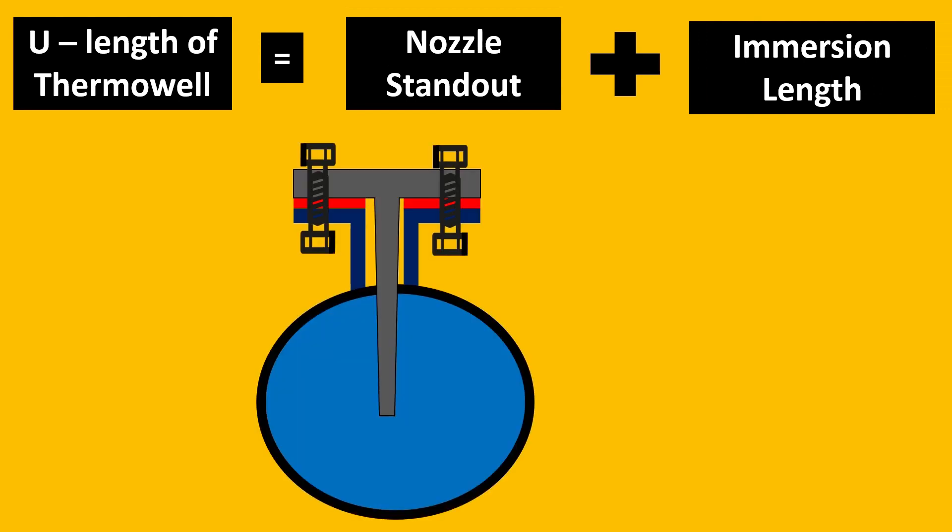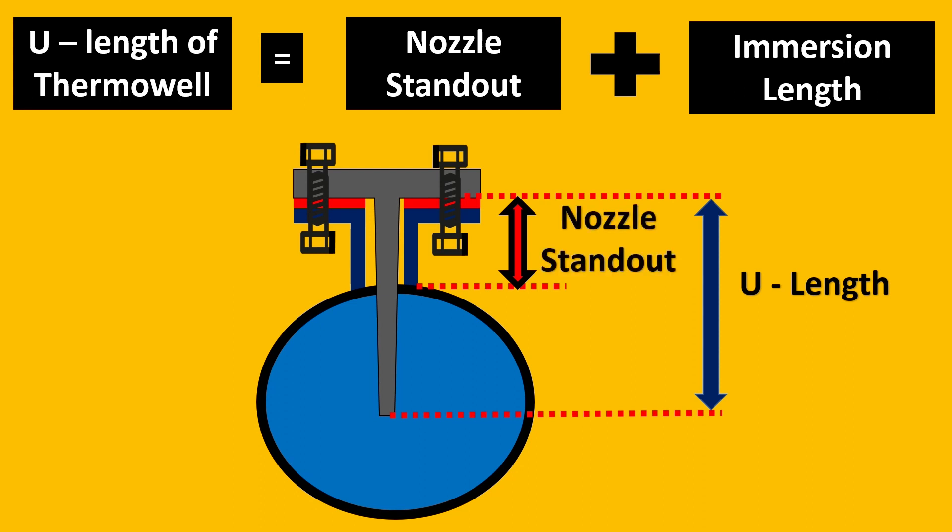Let us put this to the test. So for example we have our current thermowell which was installed. Starting from the end of the flange up to the tip of the thermowell, this is your U-length. And this can be called as nozzle standout. Nozzle standout plus how much is it immersed inside the process, or from the starting of the pipe up till the tip of the thermowell, this can be called as immersion length. So if we know both these things we can very easily calculate U-length.